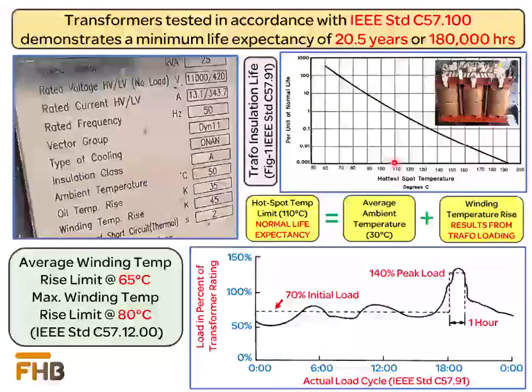As per IEEE standard C57.91, if the transformer is operated above the hottest spot temperature of 110 degrees centigrade, the rate of aging is accelerated and the life of the transformer will be reduced from 180,000 hours. IEEE standard C57.91 defines the load cycle, which a transformer may experience during 24 hours of operation. The load cycle shows that during daily operation, the transformer loading varies with time. Usually, the transformer experiences the peak load during the evening hours.